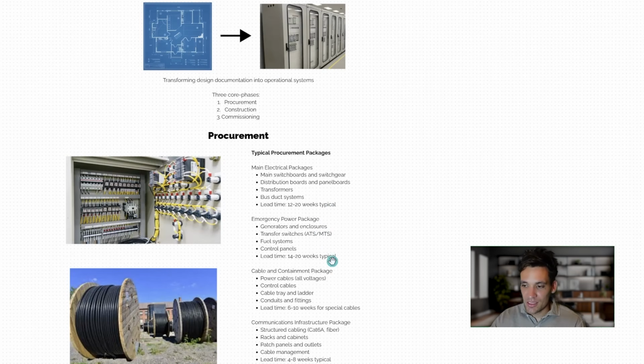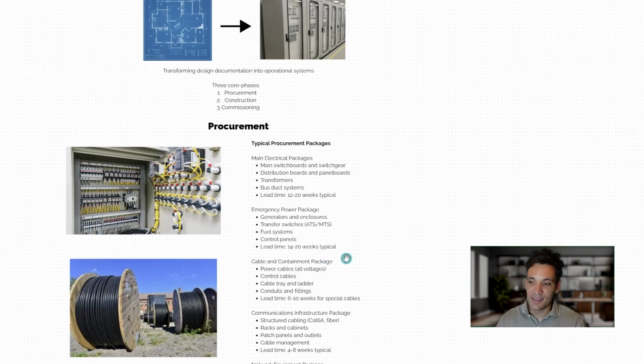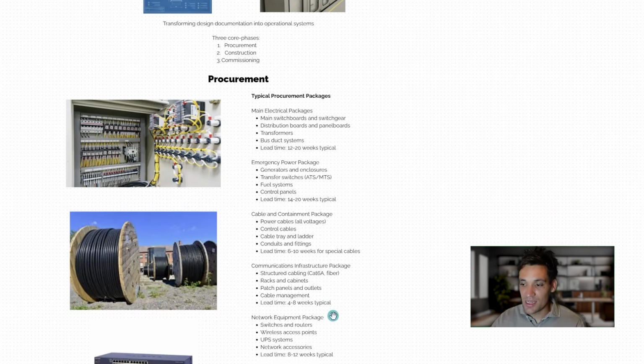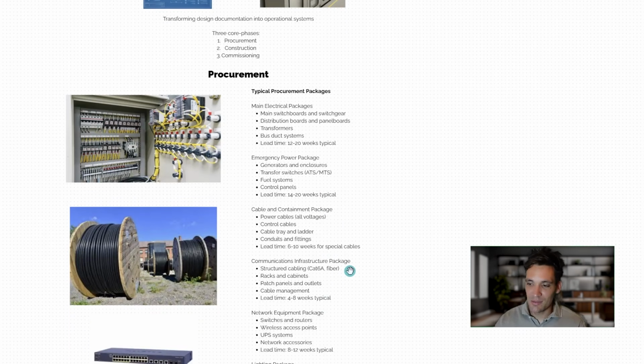Again, depending on the project, you'll typically also have an emergency power package. You might order the generator from one supplier. Transfer switch, you might order separately, or it would probably come as part of the main switchboard. Fuel system, again, might come with a generator, might be separate, and any control panels that operate this. Ideally, you'd get this for a generator as an integrated system, for a UPS as some sort of integrated system as well. You'll then need to order all your cabling and cable containment.